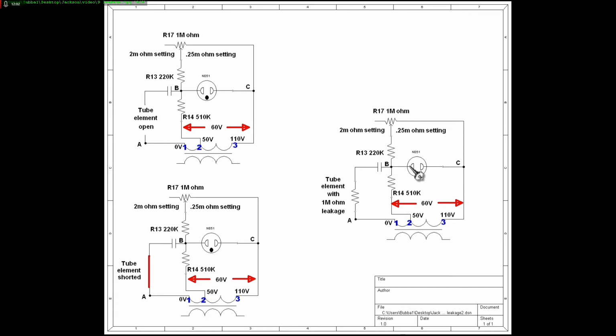But if R17's resistance is increased to 500,000 ohms, now that would be on the leakage control at the 1 megohm setting. The voltage across the neon bulb rises to about 52 volts, and the lamp will light really dim. And that indicates a 1 meg resistance short in the tube element, or between 2 tube elements being tested. So this can actually sense leakage from 0.25 to 2 megohm, and you'll get a dimly lit or flickering NE51, the neon bulb, to tell you that you have a little bit of leakage there.